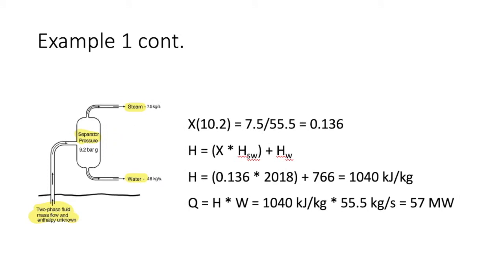The fluid enthalpy requires dryness (x) to be calculated first by dividing the steam mass flow by the total mass flow calculated previously. The dryness equation is then rearranged to solve for enthalpy, using the previously calculated dryness value and steam tables to find the enthalpies of saturated water and steam. The heat flow Q is then calculated by multiplying the enthalpy by the mass flow rate. The final heat flow is 57 megawatts.